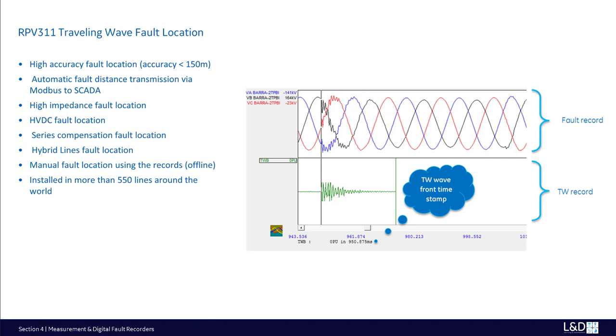The RPV311 records high-frequency traveling wave. The data is then processed by the DR Manager software, which automatically downloads the records, calculates the fault locating, and makes it available with a Modbus for SCADA communication. Maintenance crews are thus directed to the exact location of the fault without need to resort to vehicle, helicopter, or foot patrol to find the exact location. Worldwide, there are over 550 lines that have installed the RPV311 traveling wave fault locator as of 2020.